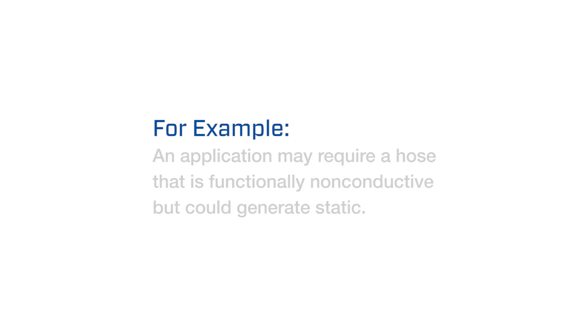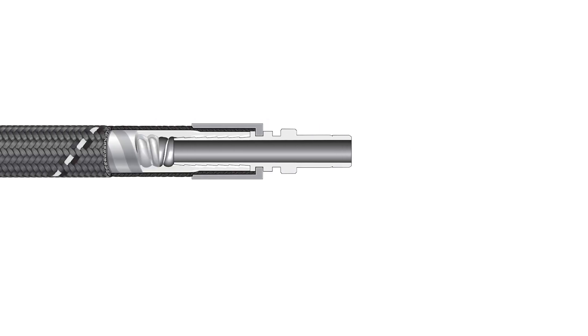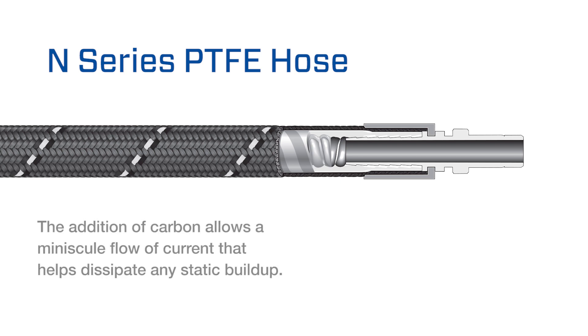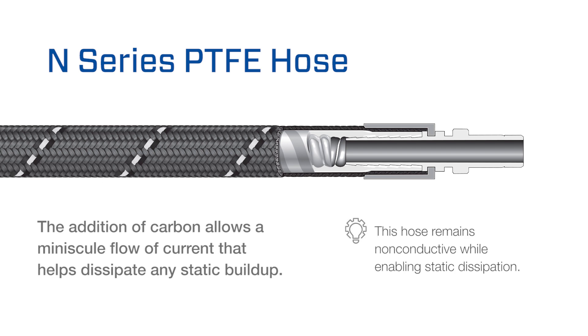For example, an application may require a hose that is functionally non-conductive but could generate static. An effective way to enable soft core hoses to dissipate static is to infuse them with a carbon material. The addition of carbon allows a minuscule flow of current that helps to dissipate any static buildup, allowing the hose to remain functionally non-conductive while simultaneously enabling static dissipation.